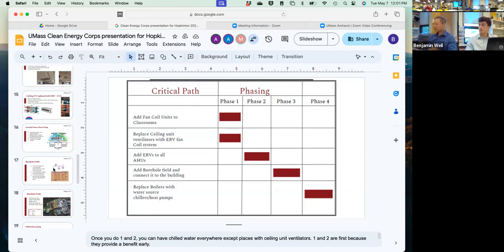It is not necessarily the case that it is the very best possible system, right? So if you did a test well and you found that you had what they call competent rock, which is to say you drill down and all of a sudden you hit bedrock and it's nice and solid stuff, and it's got lots of cracks in it, and you've got an aquifer running underneath, you might find that the best kind of well is what they call a standing column well. And that would allow you to have fewer boreholes, right, fewer wells. And so they maybe take up less space, right? And higher efficiency.